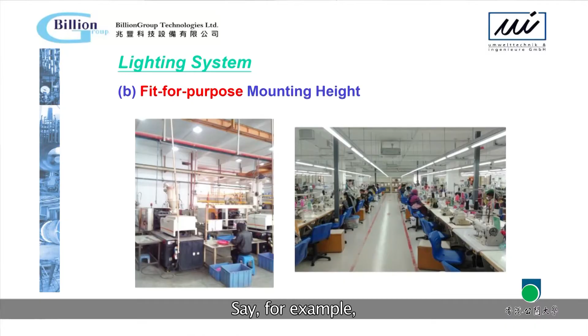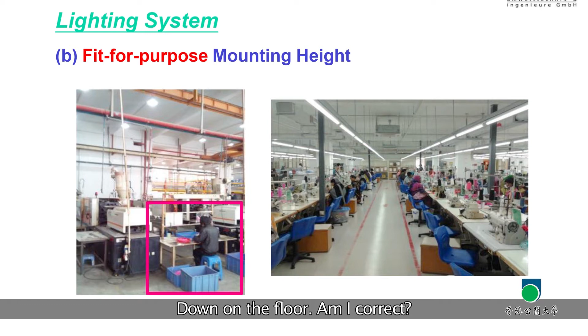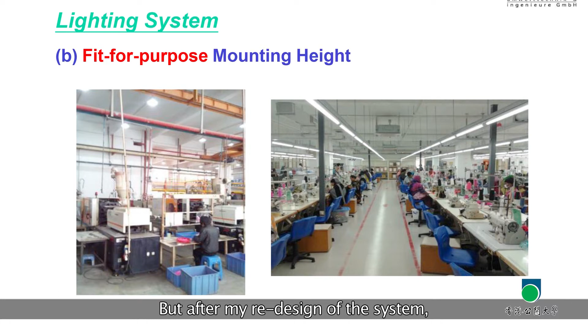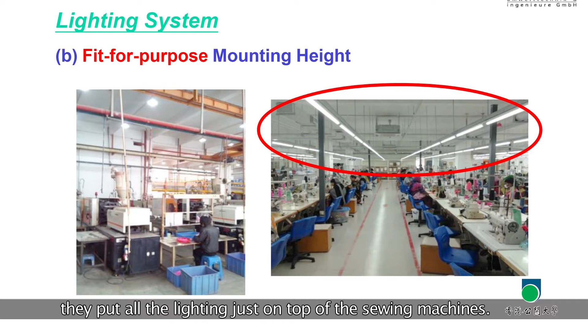For example, in this factory the lighting is at the ceiling of the plant room, but where is the task actually carried out? Down on the floor, correct? If you put the lighting on the ceiling, you waste a lot of energy - even though the lux level up there might be 1,000, down at the floor it's only 50. You're wasting energy illuminating areas with no task. In this picture, all the lighting was originally at the ceiling, but after my redesign, we put all the lighting just above the sewing machines. By doing so, we saved more than 50% of the energy.